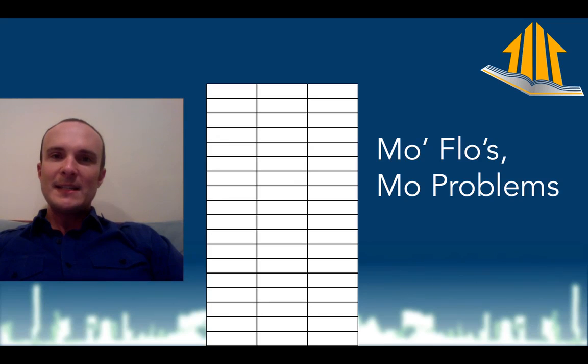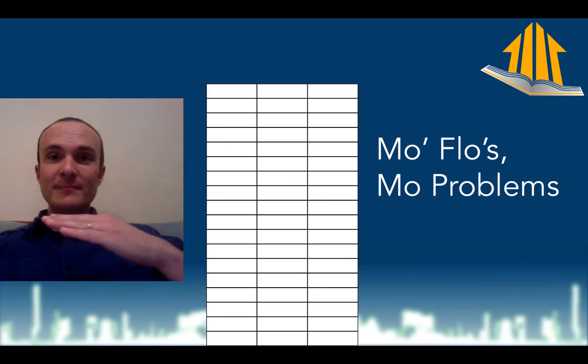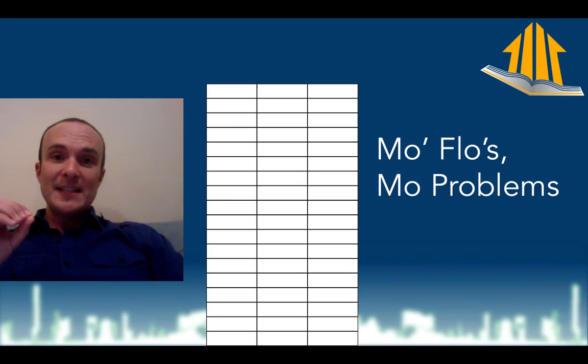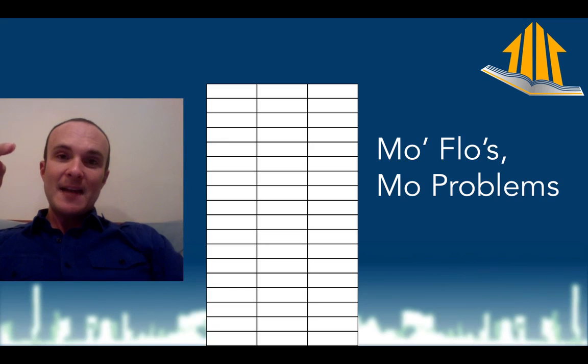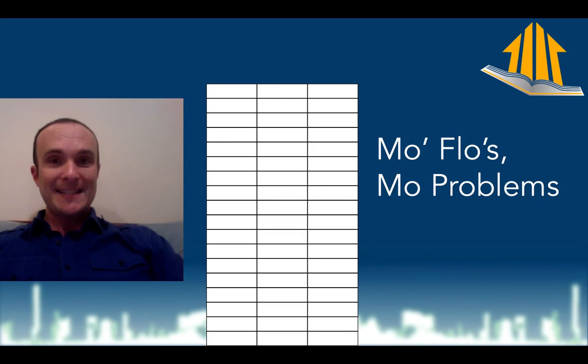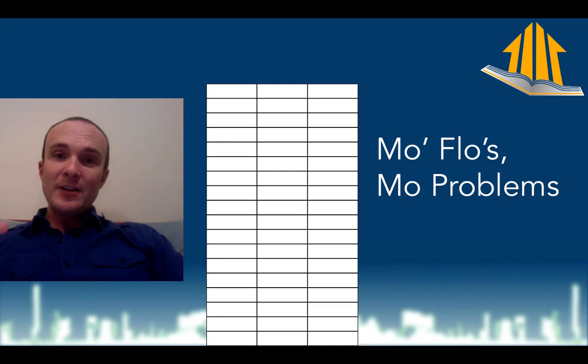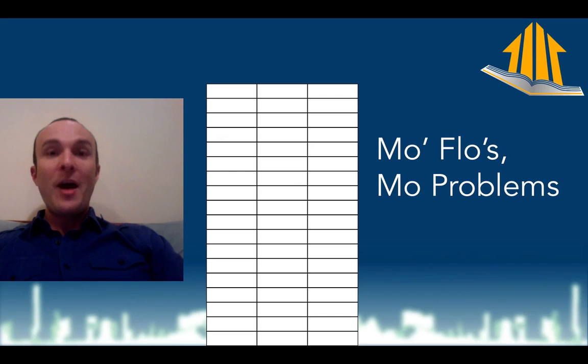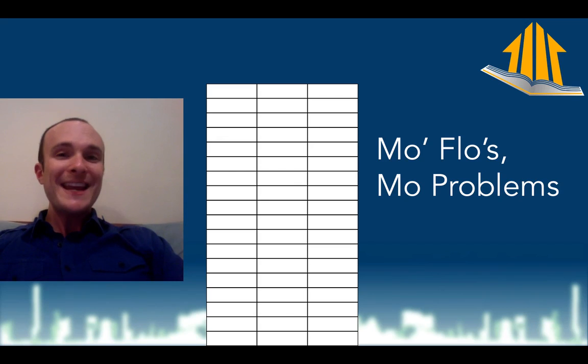160 pascals is actually more than twice the blower door test pressure on both the bottom end and the top end. In the middle of the building, there's going to be your neutral pressure plane — where it's the same pressure inside as outside, which is zero. So you'd have plus 75 pascals at the top and minus 75 pascals at the bottom. 75 pascals is significant because that is the test pressure you're going to be building to. So when you're already at negative 75 pascals at the bottom, you're going to have to push to negative 150 in order to bring the entire building to your pressure.